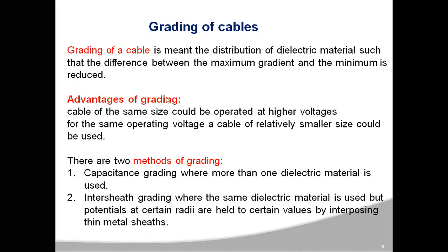By using grading of cables, a cable of the same size can be operated at higher voltages. Suppose you use one single cable, then the operating voltage will be less when compared to the graded cables. Okay, and for the same operating voltage, a cable of relatively small size could be used. Okay, if the operating voltage is the same and you use the grading of cables, then the size of the conductor will decrease. So these are the advantages.